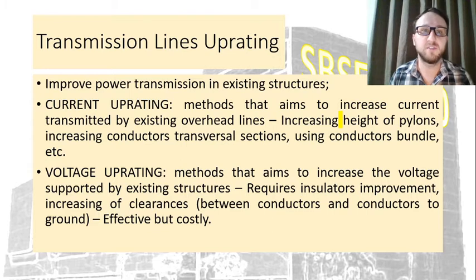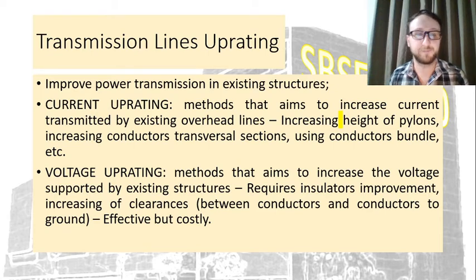In the literature on transmission line uprating, we have the current uprating method, which aims to increase the current, but involves some problems like increasing the height of the pylons, increasing the conductors' transversal sections, and using conductor bundles, etc. Another technique is voltage uprating. It uses the existing structures, requires insulator improvement and increased clearances, and could be costly.